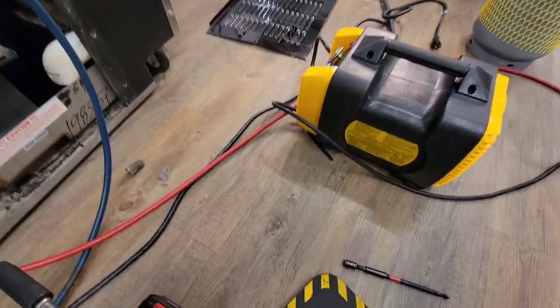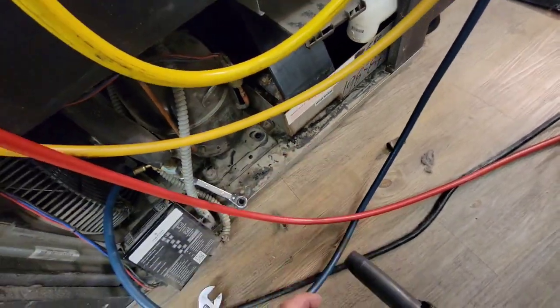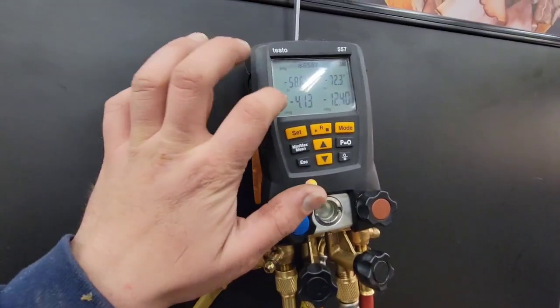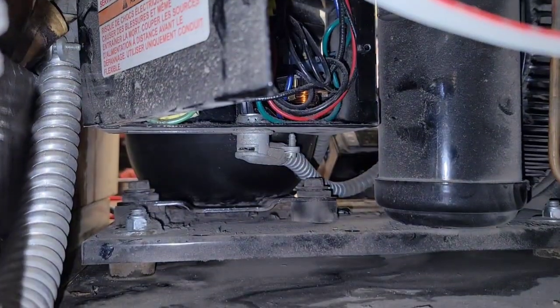While I'm recovering the refrigerant, I'm going to unbolt the compressor. I recovered all the gas out of it — it's in a little bit of a vacuum. You can recover it down to about 1 psi, that's fine. You can see there are two more bolts back here for the compressor.